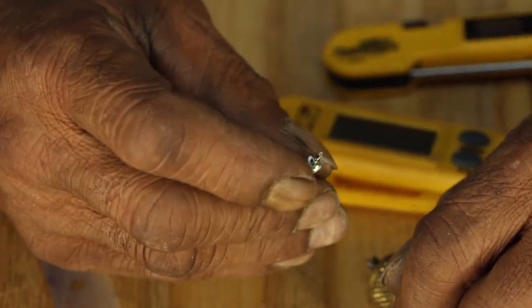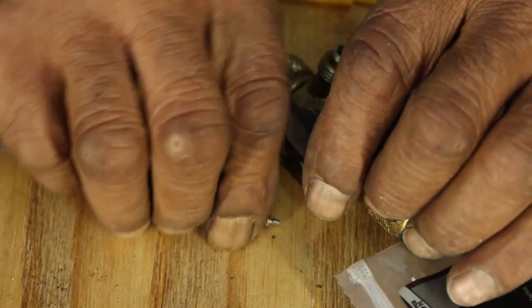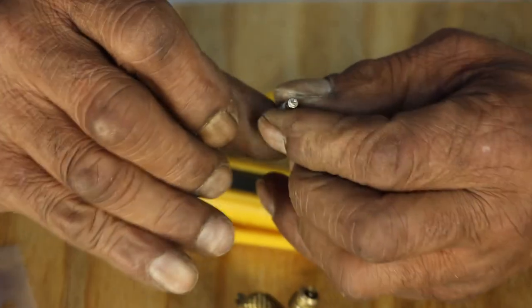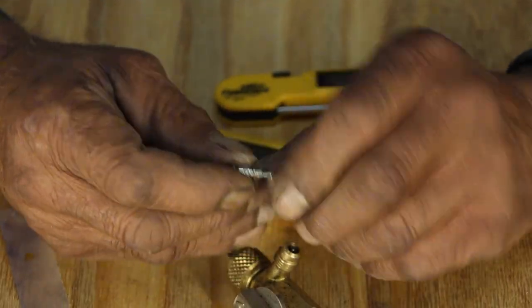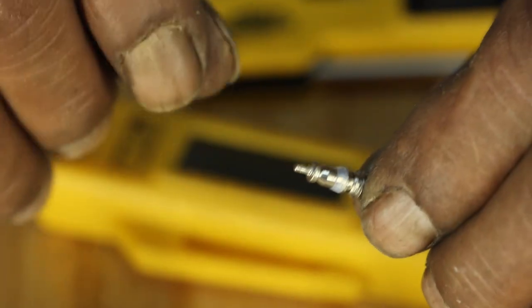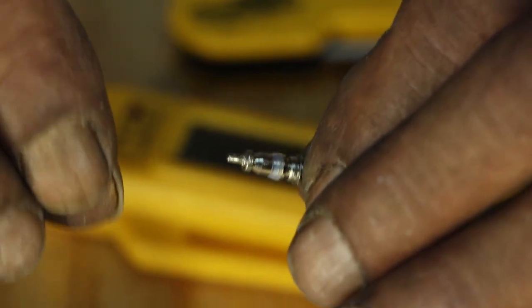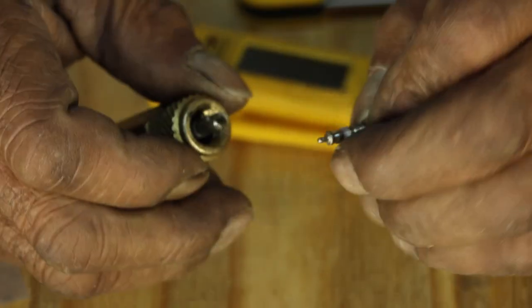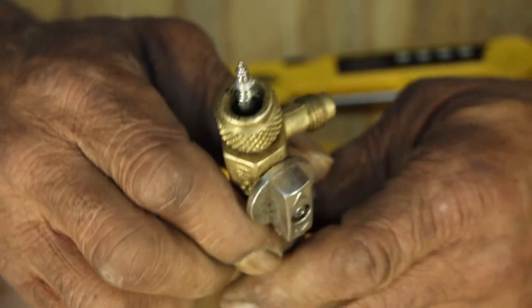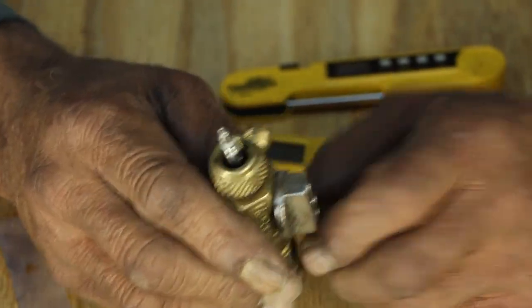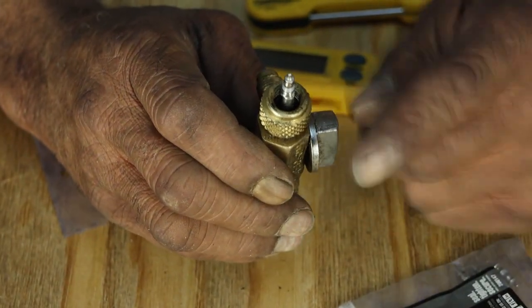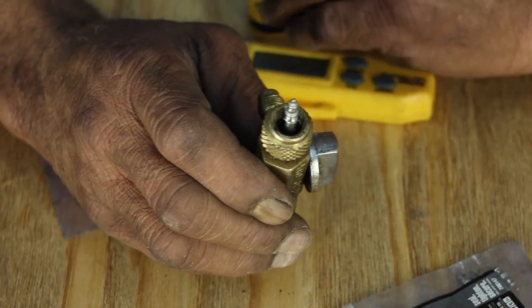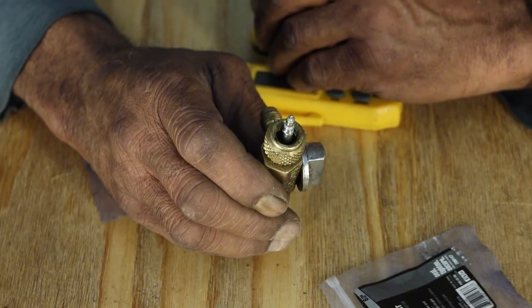Well, these are also used in our service ports on our air conditioners because this has a little spring action within it that allows it to open and close. And I'm sure you can't see that. But in my service port, on my outdoor unit, where I hook my gauges, there is a Schrader valve. Sometimes I need to remove that Schrader valve, and that's when I need this tool. But this tool also, if a Schrader valve goes bad on a system that is fully charged with Freon, if I take that Schrader valve out, there's nothing to stop the Freon from leaking.